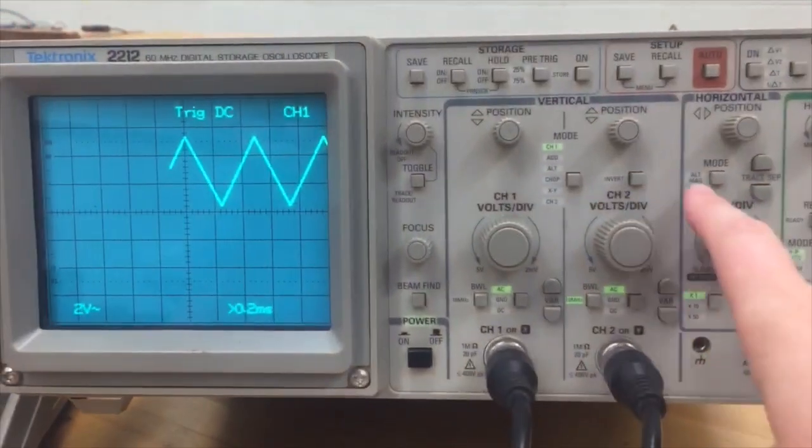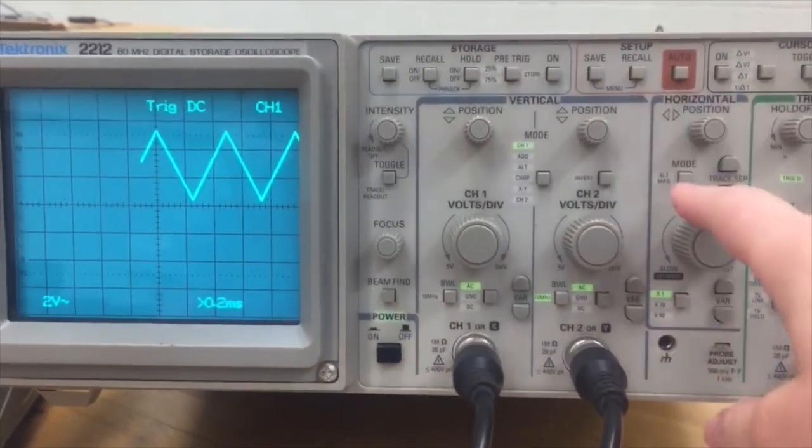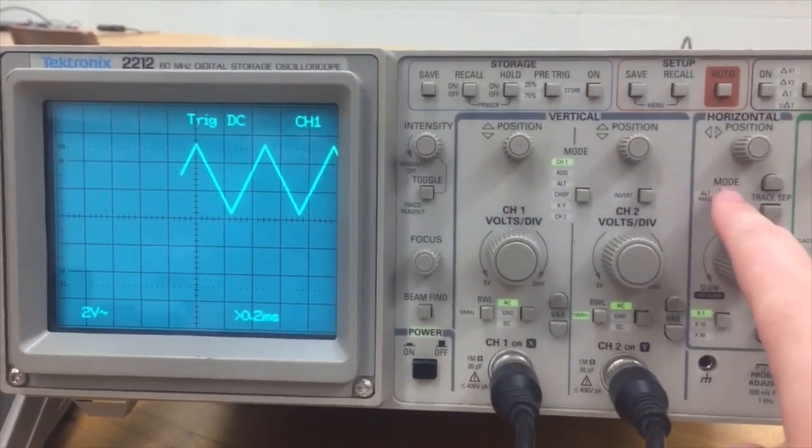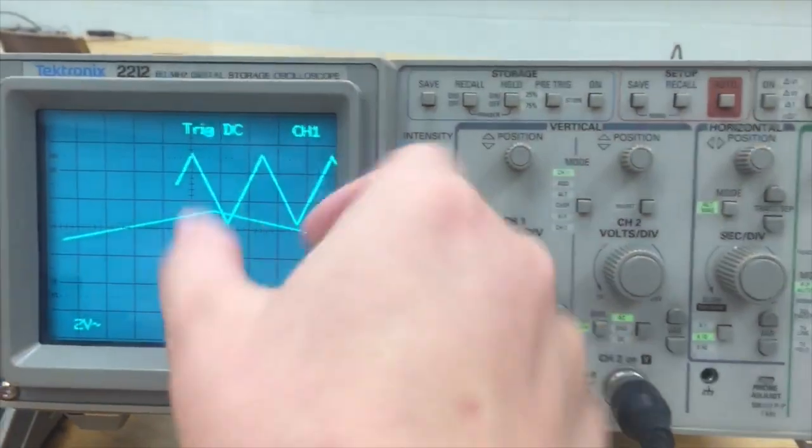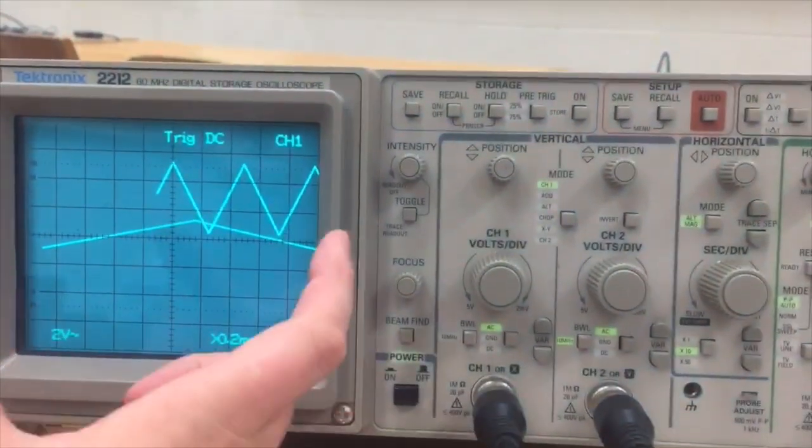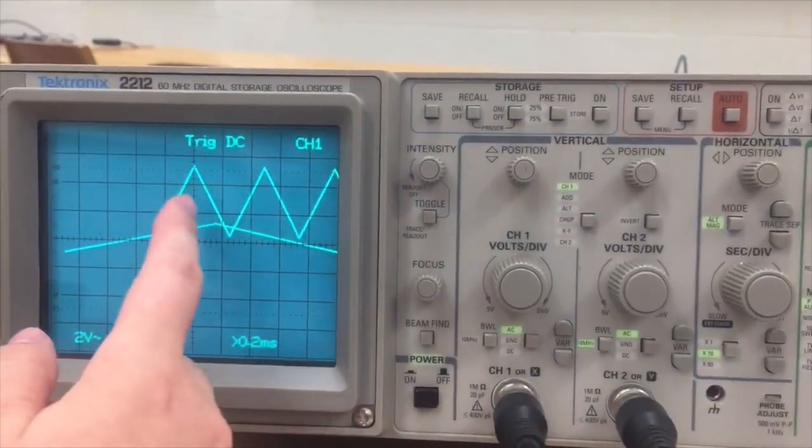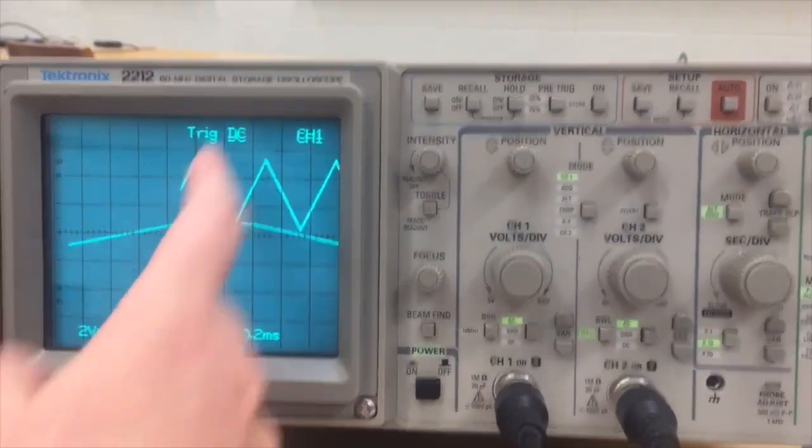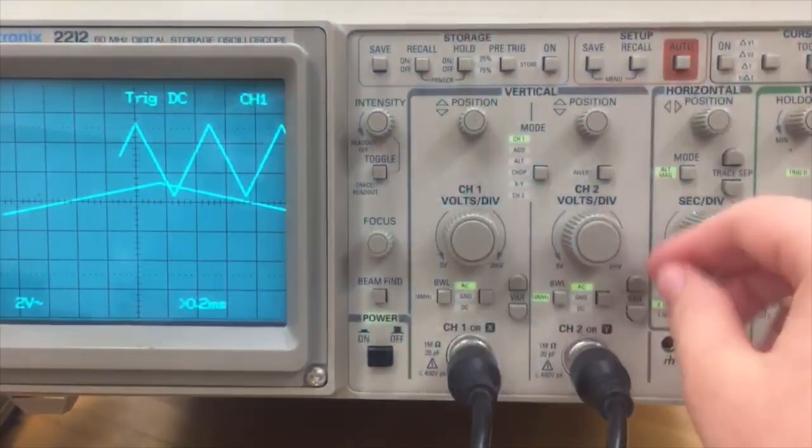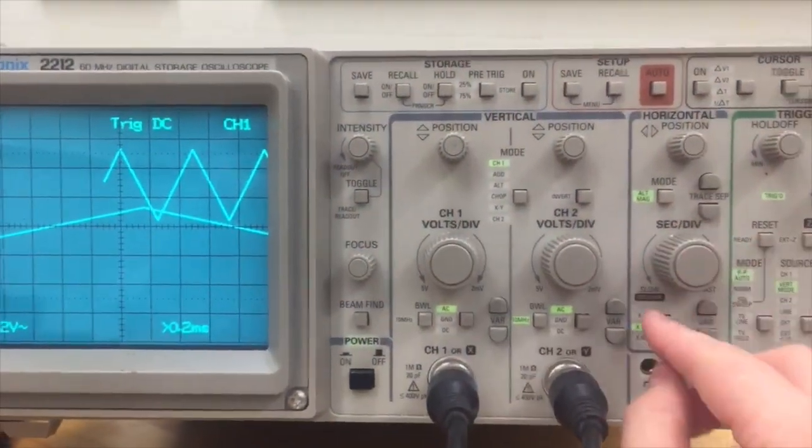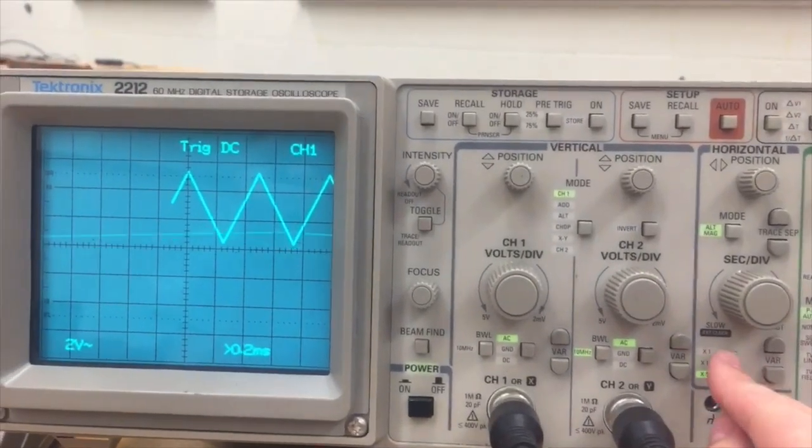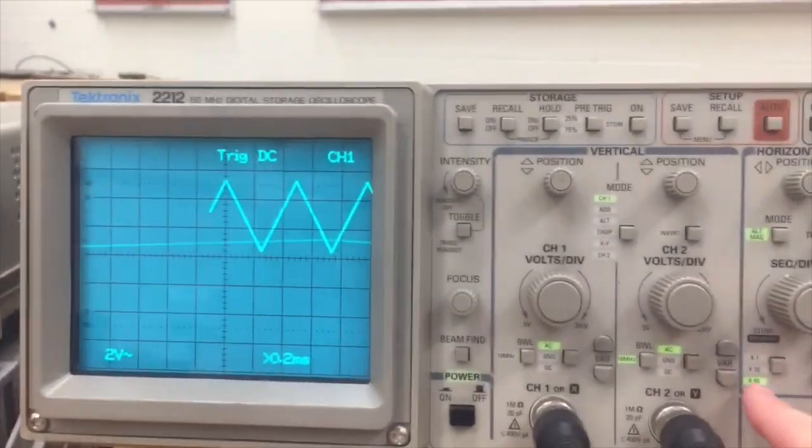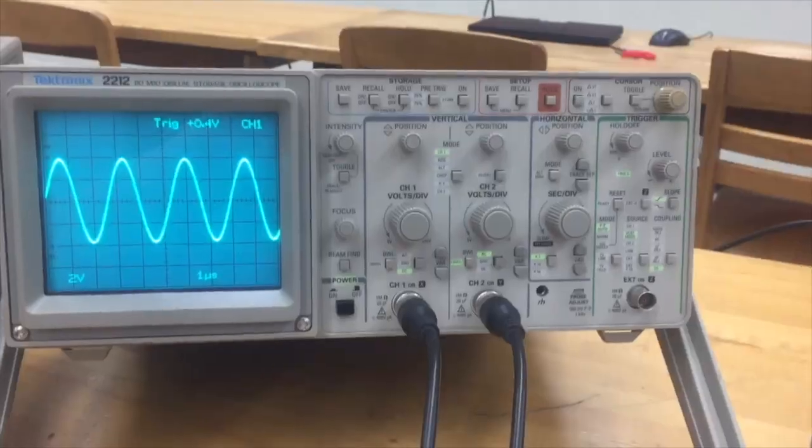The alt mag mode is found underneath the horizontal, and what it does is zoom in a portion of your signal, and you can zoom it in one times, ten times, or fifty times.